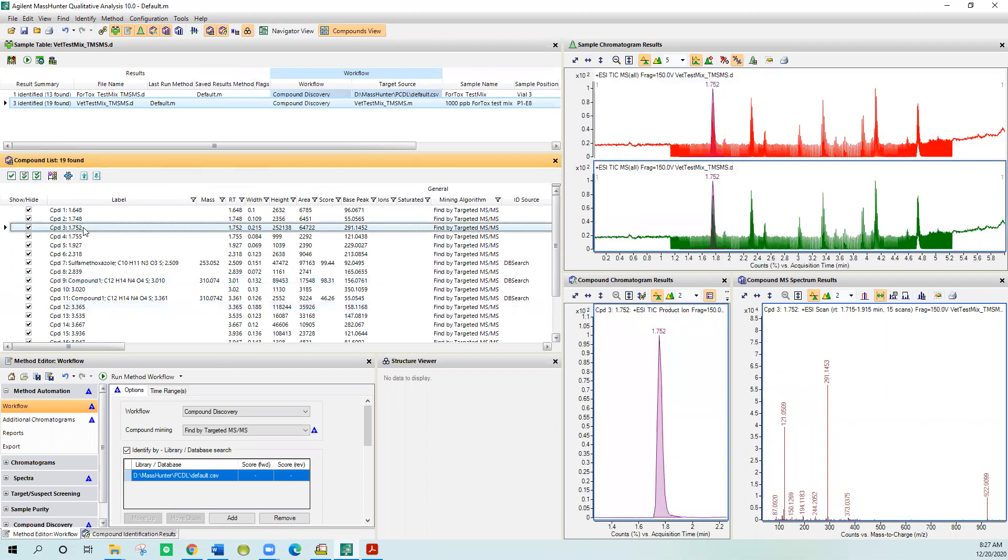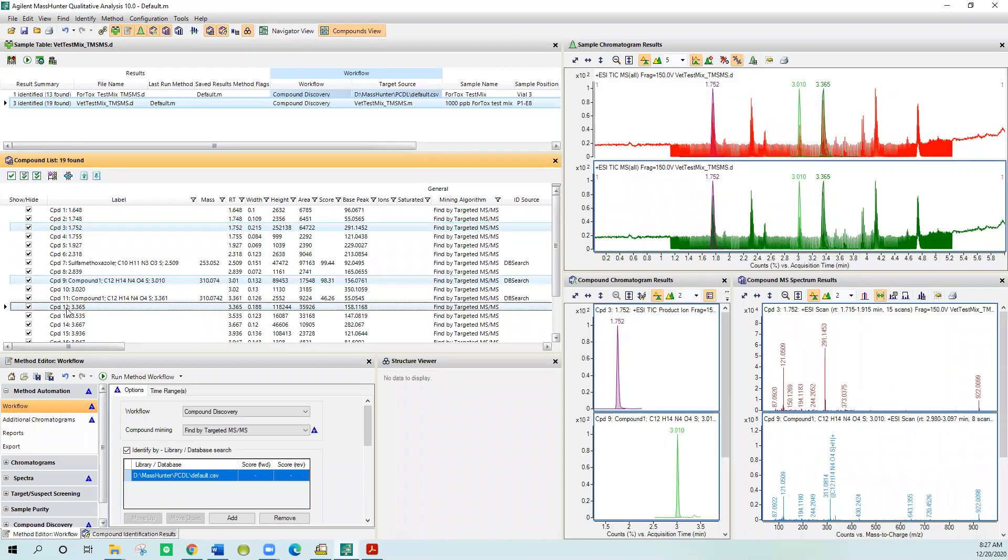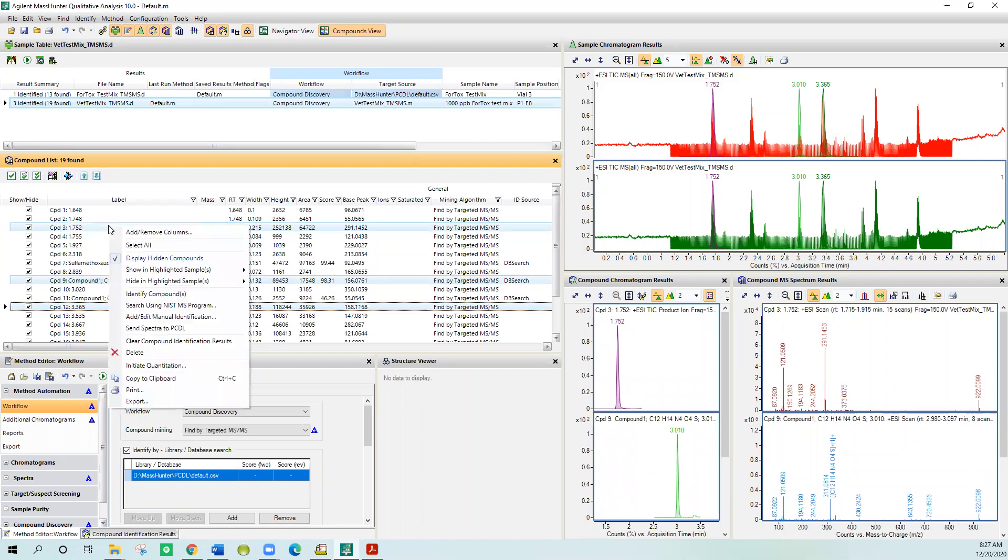I want to take some spectra into the NIST search and search. In this case, you can select some single spectra just by left mouse clicking on one, but I want to do three just for a little bit more efficiency. So I'm going to pick three, holding the control button on my keypad so I can select more than one. I've selected now three. You can see they're highlighted: three, nine, let's do twelve also. Now after I have them selected, I right-click on any one of the selected ones and say search using NIST MS program. It will send all three over into the NIST search software.